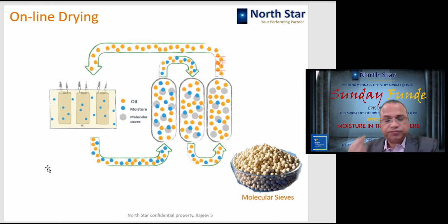The second system is online drying. This is a kind of passive system which is put on the transformer, and even when the transformer is in charged condition, without interrupting the performance or power delivery of the transformer, this system keeps on working. It is based on the principle of molecular sieves. Molecular sieves are basically mechanical filters with molecular pores inside. In this particular one, the pore size is around 3 to 4 angstrom, and because of such small pores, the moisture is trapped in the sieves and only oil is allowed to pass through. The wet oil comes in, passes through this molecular sieve system, and only dry oil is pushed back into the transformer.